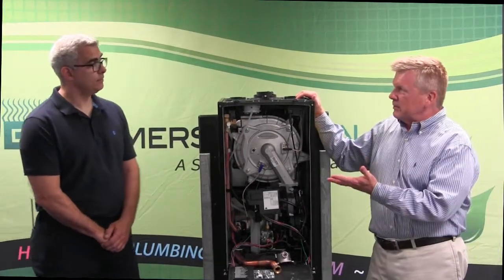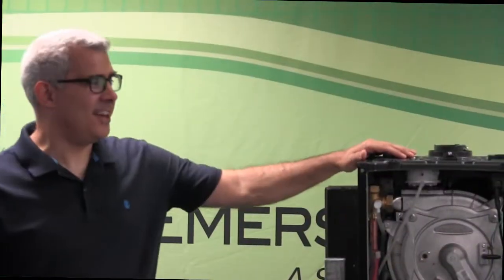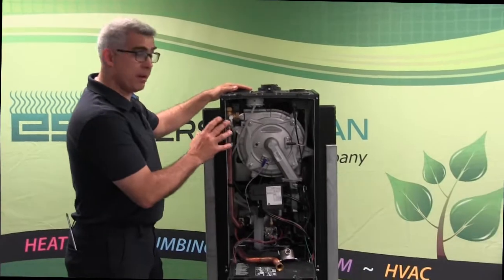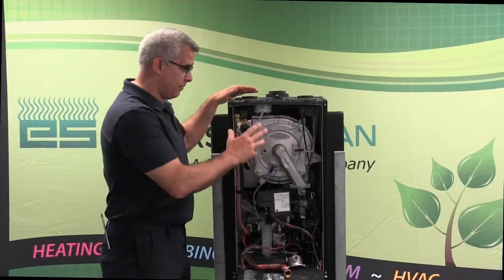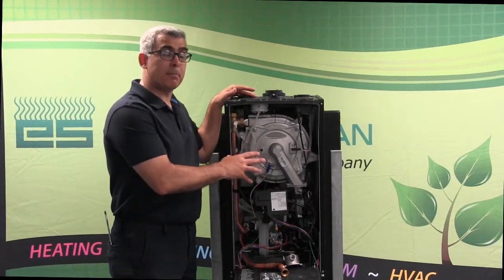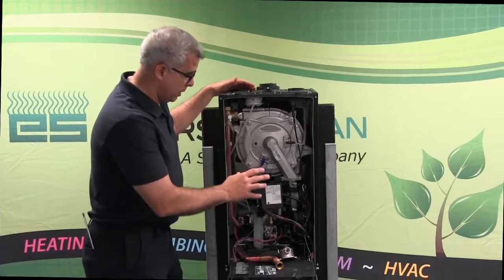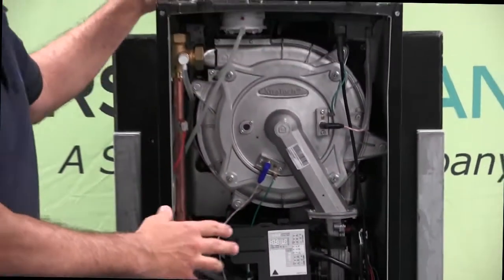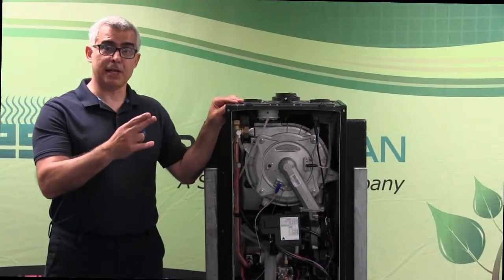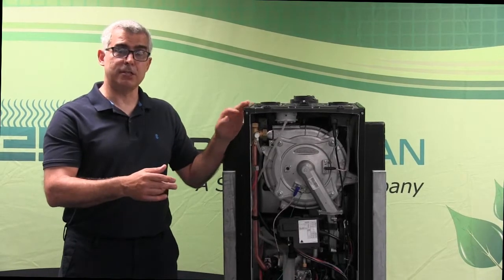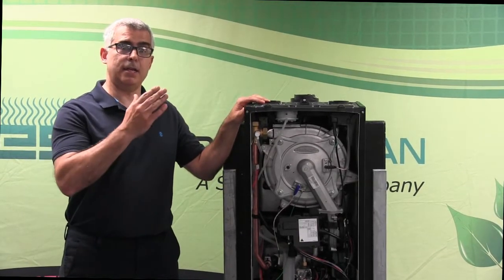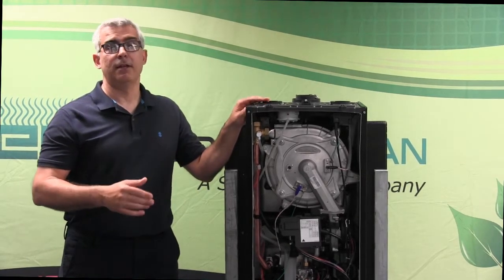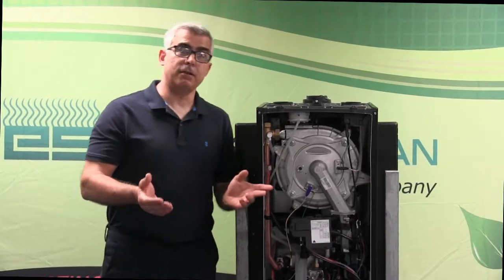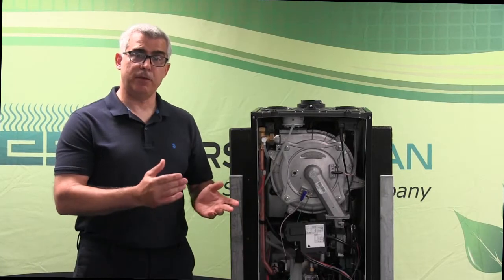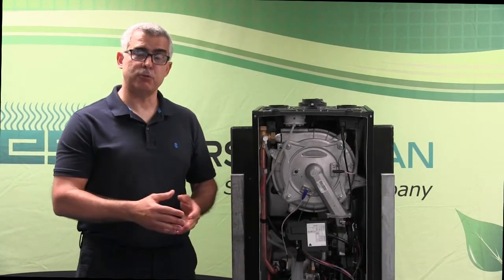So Mike, why don't you tell us a little bit about some of the new equipment that's out there and what's coming? Okay, thanks, Mike. And what I want to also go over that I think is a great point here is that Ariston makes 95% of the parts that are in this. Also, by making the parts, they control the quality, which is huge. The other thing is that they have a Taco ECM pump included in the package, made from Taco Italia, and they work directly together. Now, as far as sizes of the boilers, we have 2 boiler sizes out currently and 2 combi sizes. The 2 boiler sizes are 85 and 120,000 BTU input, and the combi sizes are 120 and 150,000 BTUs. What we have coming up at the end of August and early September, we will have 2 more boiler sizes, the 155 and the 199, and also 1 more combi size, which will be the 199.